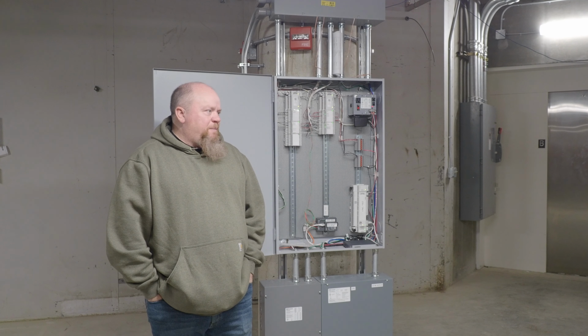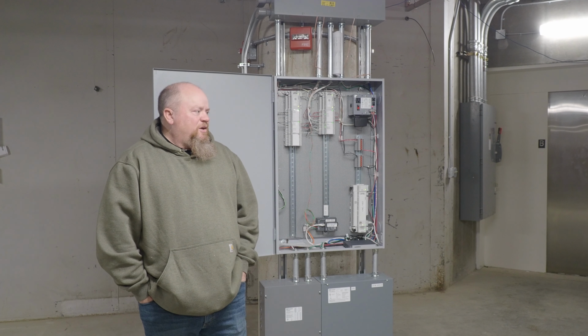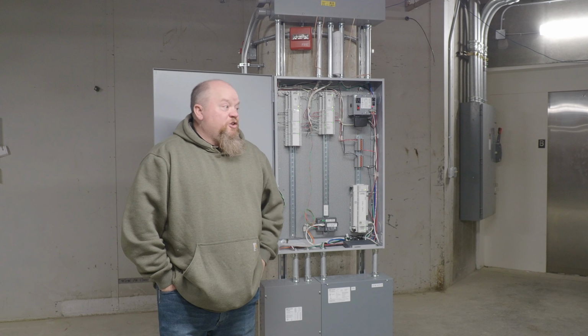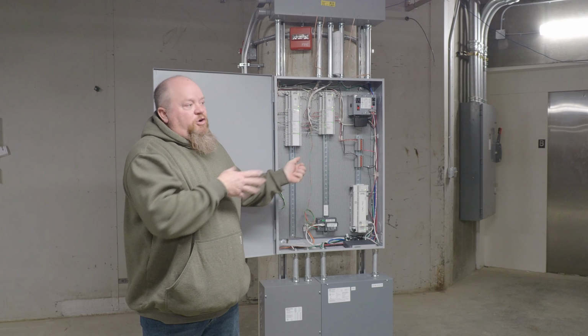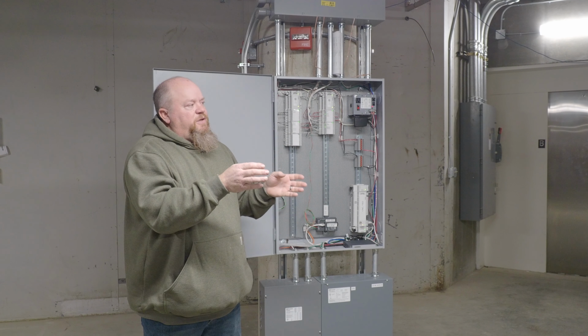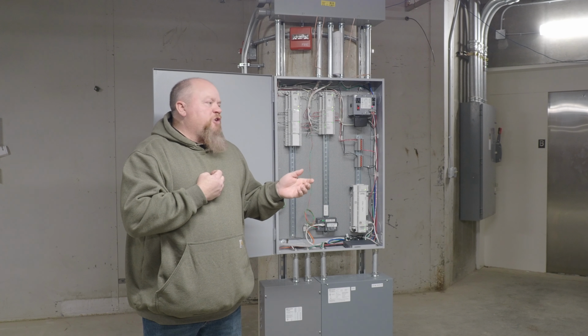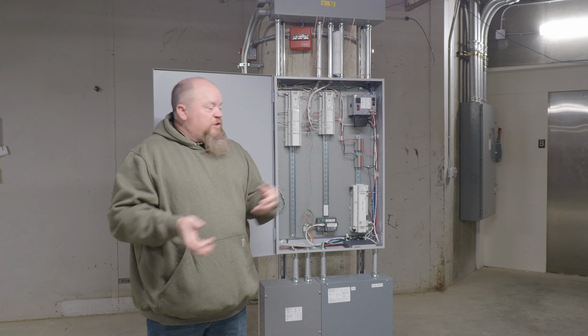So we have a mag meter in the back, because I think somebody asked a while ago, why is the boiler pump always running full speed? I think you asked Jason and Jason asked me. The reason is, we don't control the boilers, we enable the boilers, we want heat. Aerco says, okay, I need to run 2 boilers. Aerco opens the isolation valves on the 2 boilers. I get an end switch that says the valve is open. I need to maintain a certain amount of flow for those boilers, so I ramp it up.